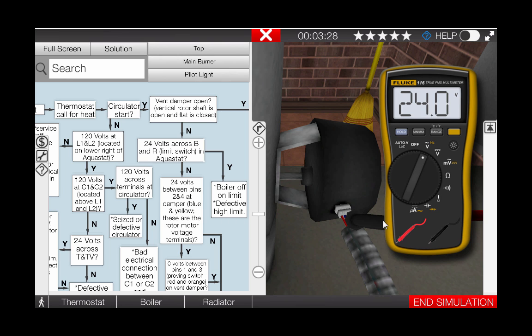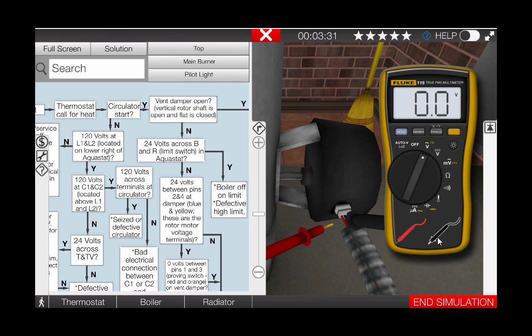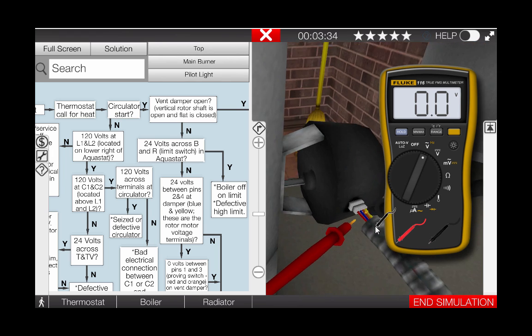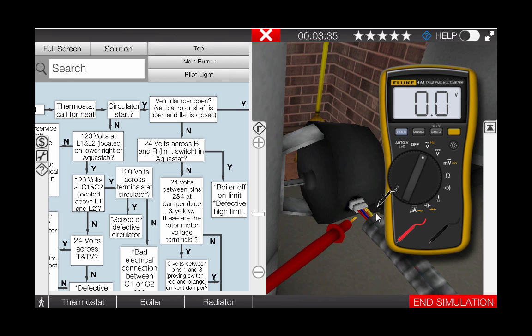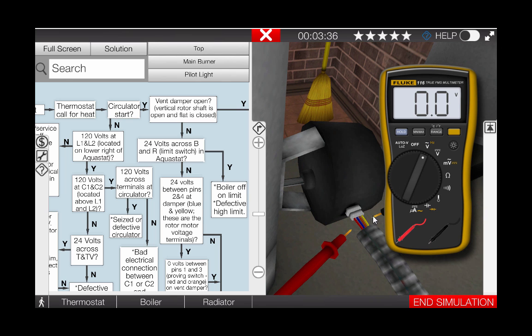This can be done by simply clicking the meter leads and placing them on the red and orange hot spots. A reading of 24 volts across this switch indicates that the switch is open.